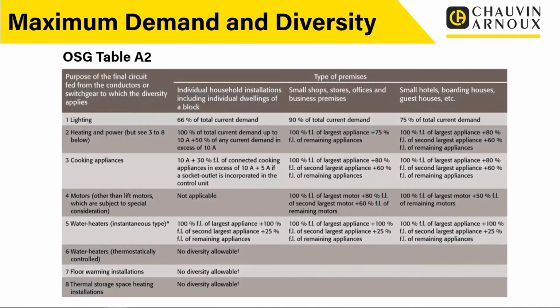So you'll remember, probably going back when you've done some training in the past, from the On-Site Guide, we've got table A2, and in table A2 it lays out some general rule of thumb logic we can use if we're laying out an installation. And to be honest, if we're designing an installation from scratch, this may be the way we have to do it, because we don't have any data we can actually measure.